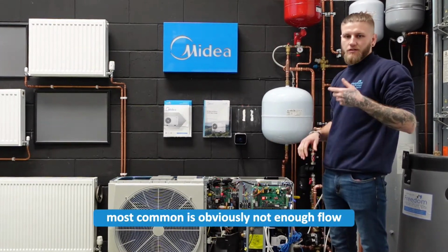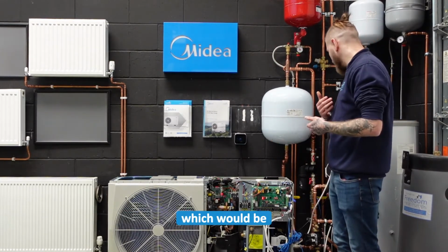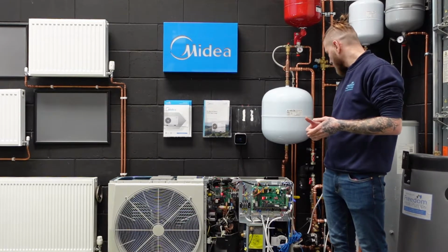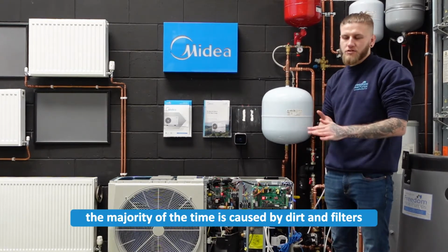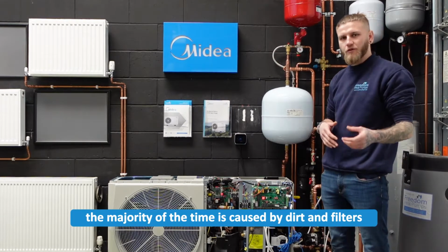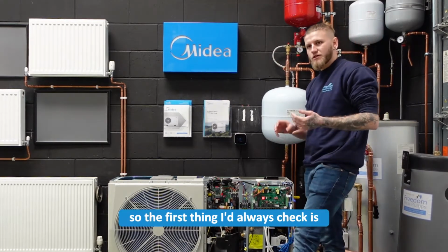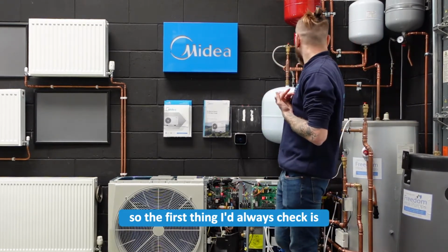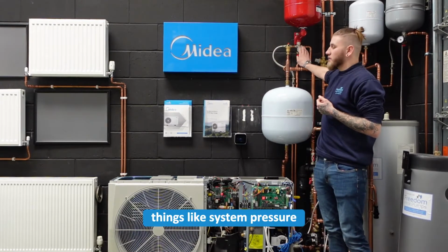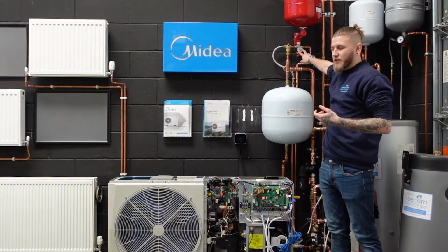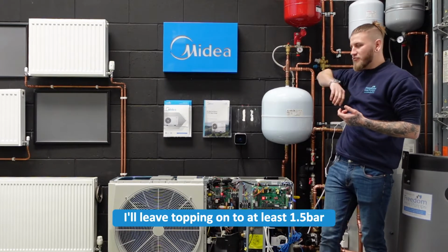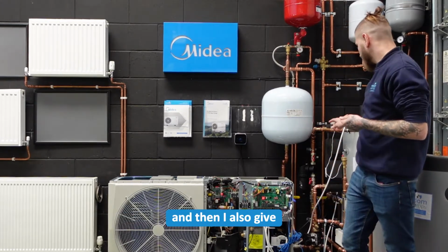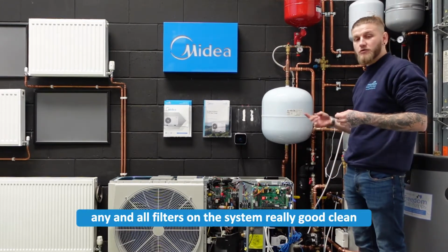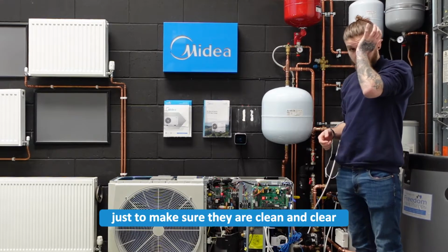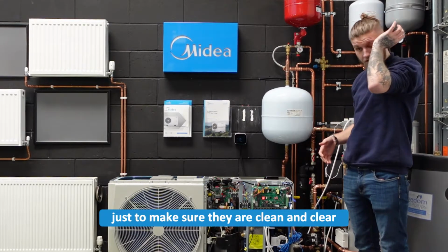Most common is obviously not enough flow, which the majority of the time is caused by dirt and filters or air in the system. So the first thing I'd always check is things like system pressure. If the system pressure's dropped, then that'll need topping up to at least 1.5 bar. And then I'd also give any and all filters on the system a really good clean, just to make sure that they are clean and clear.